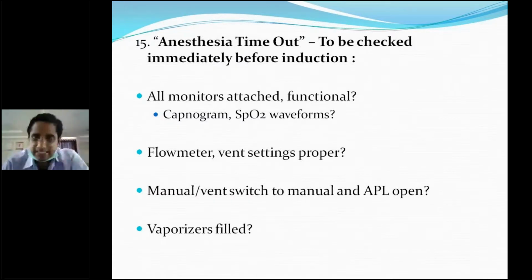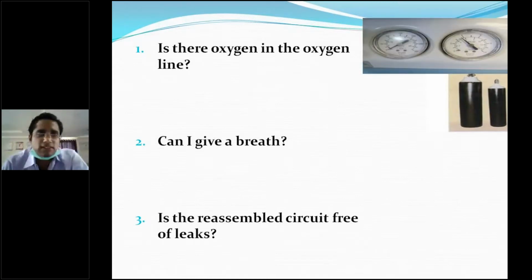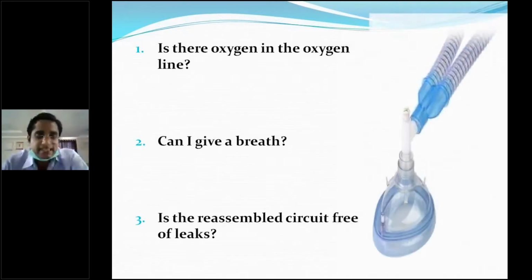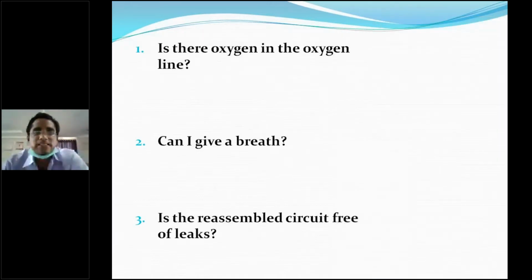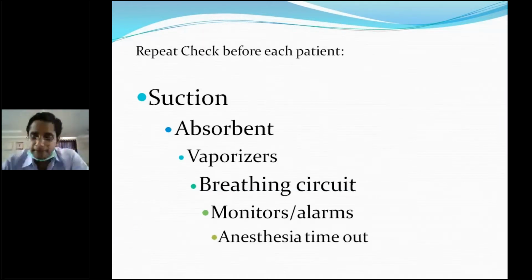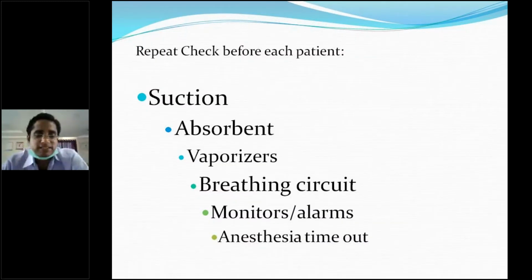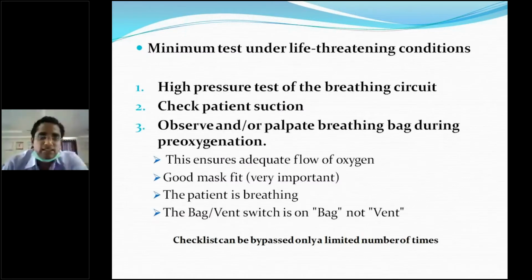You need to check this machine completely, and you need to check whether there is oxygen in the oxygen line. Can you give a breath to the patient? Is the reassembled circuit free of leaks? And repeat this for every case. Before giving anesthesia for any patient, you need to check the suction, absorbent, vaporizers, breathing circuit, monitors, and say anesthesia timeout.